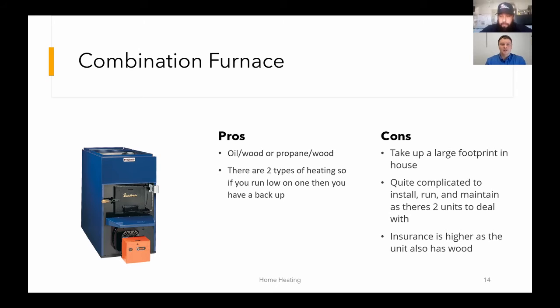A fresh air intake, or combustion air, is really important with these units. I've seen cases where they've overheated and warped the doors, and then they don't work properly. It's just making sure it's two units you have to maintain instead of one, which doubles the maintenance required. Again, a great unit if the customer is versed in the maintenance and upkeep and shown how to use them properly, but they are big units and costly to maintain, especially in northern communities with limited access to technicians.